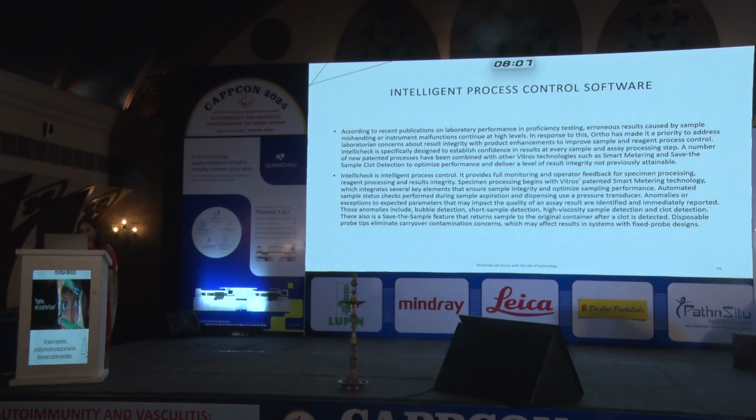These anomalies include bubble detection, short sample detection, that is QNS, high viscosity sample detection that can occur in case of lipemia or presence of paraproteins, and clot detection. There is also a save the sample feature that returns the sample to the original container after a clot is detected. That is, sample is not unnecessarily wasted.